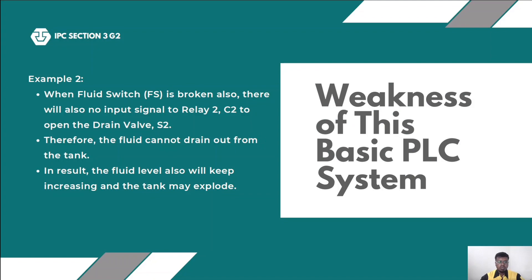Continuing with example 2: when the fluid switch is broken, there will also be no input signal to Relay 2 to open the drain valve S2. Therefore, the fluid cannot drain out from the tank. As a result, the fluid level will keep on increasing and the tank may explode. That's all for me, thank you.